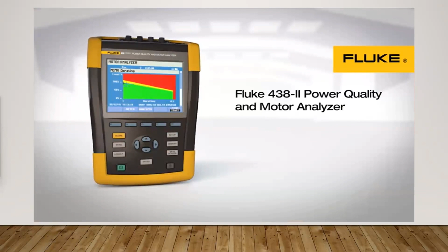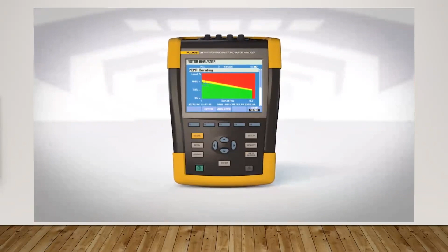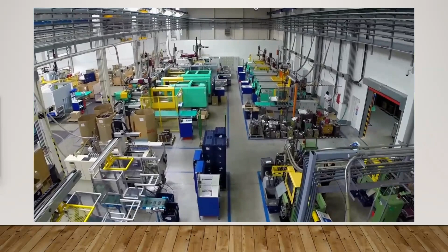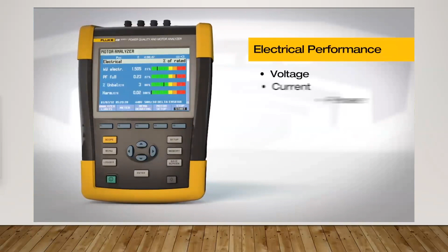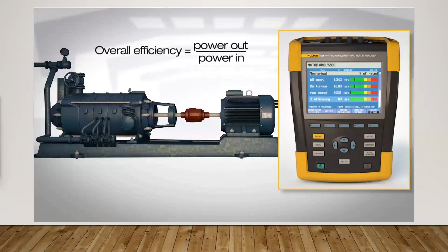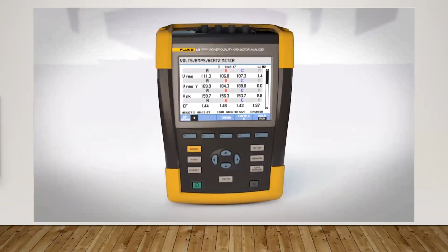Introducing the Fluke 438 Power Quality and Motor Analyzer. The Fluke 438 is a multi-purpose test tool designed to improve troubleshooting on electric motors and minimize downtime. Whether you're in a process plant or discrete manufacturing, electric motors are critical to your operation's success. The Fluke 438 lets you quickly gauge electrical performance, power quality, and mechanical performance of industrial motors. Using three-phase electrical measurements on the input and motor rating plate data, it calculates torque, the most critical mechanical performance variable, along with speed, load on the motor shaft, and overall efficiency, without needing to install mechanical sensors. All this with a single tool, and all while the motor is running, so you don't sacrifice uptime.